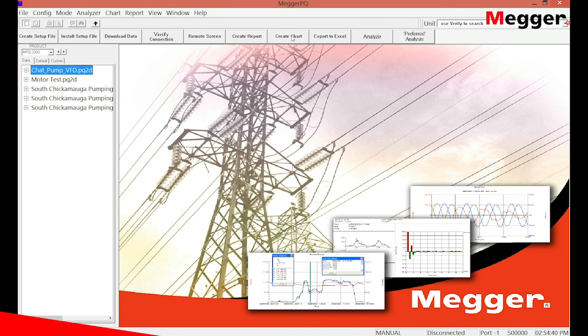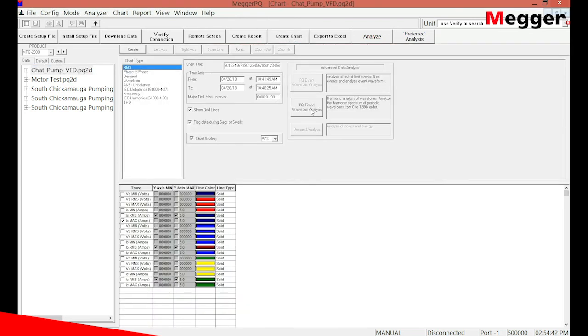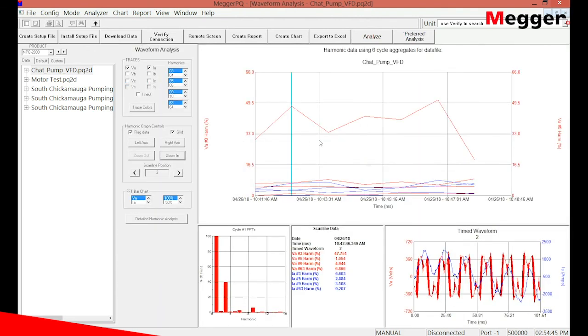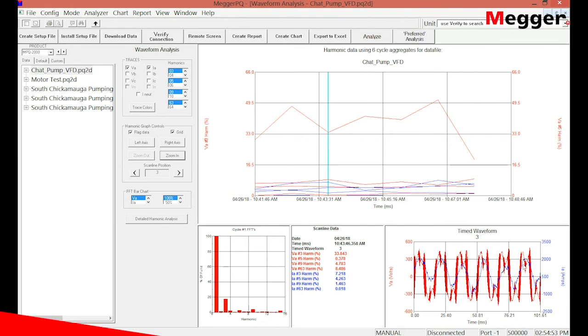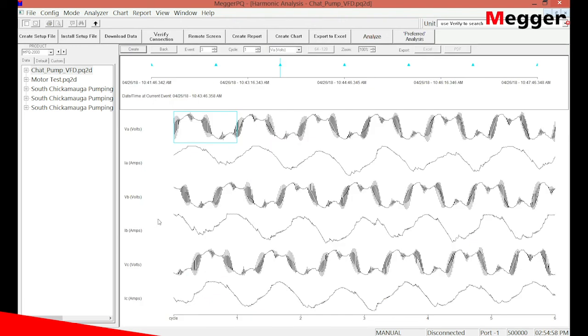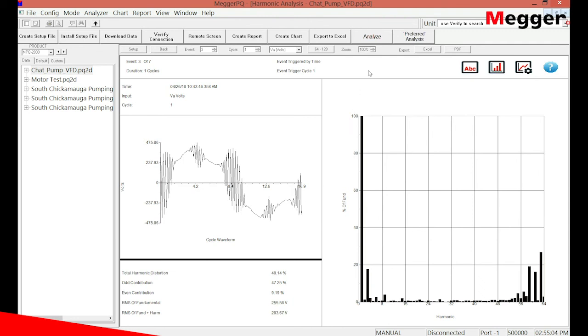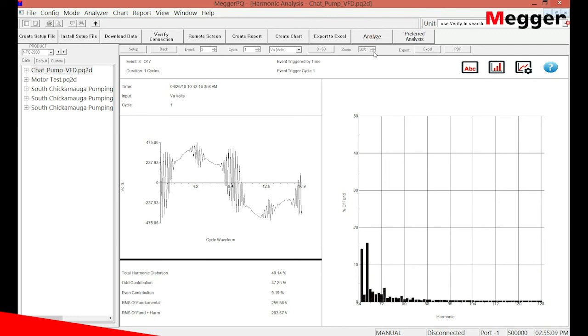Using the timed waveform recording scope ability, I can trend all the captured waveforms. I can trend them based on different harmonic orders. I can scan through them and examine each waveform. And with the click of a button, I can perform a detailed harmonic analysis. I choose the cycle, and I can see the harmonic content. I can view the harmonic content through the 128th order. And I can see that this VFD had harmonics up to the 67th order. We can then create a report with just the click of a button.